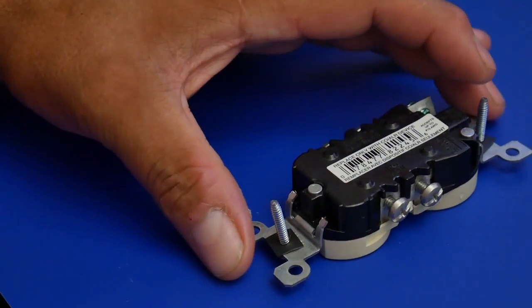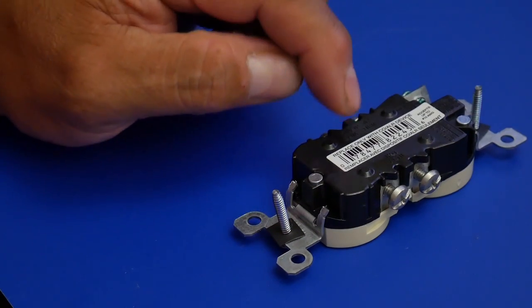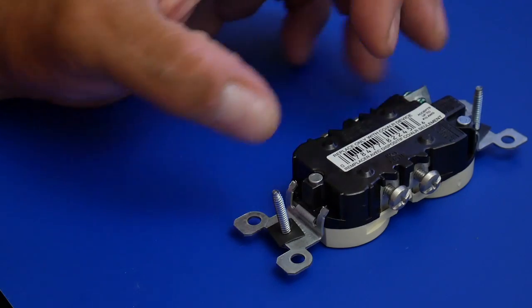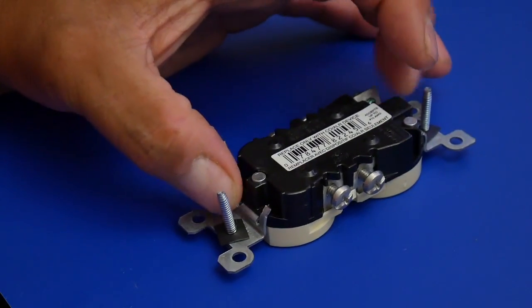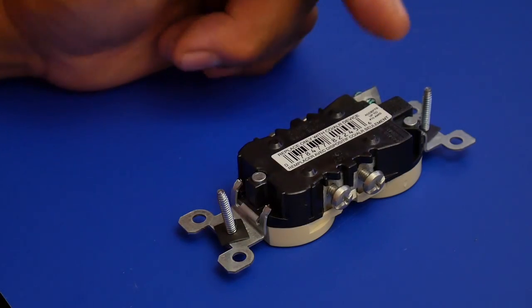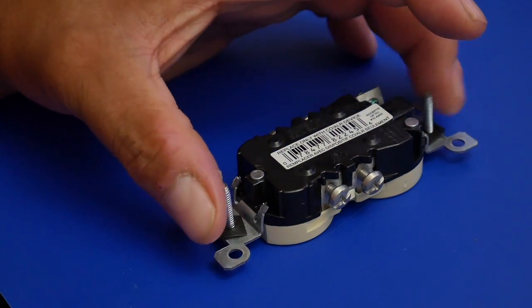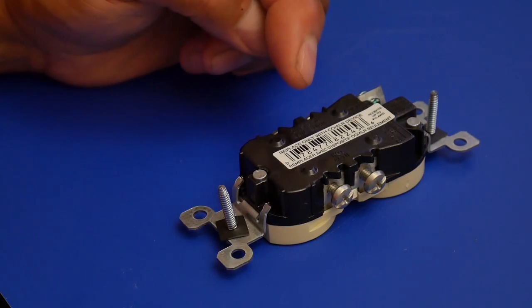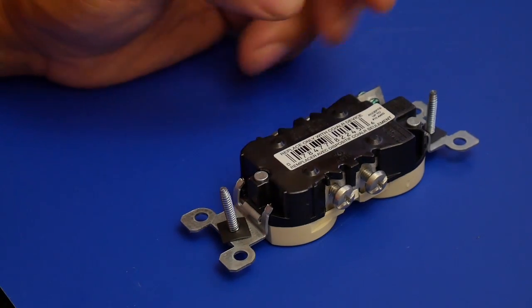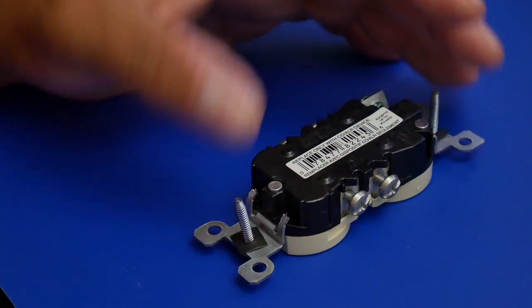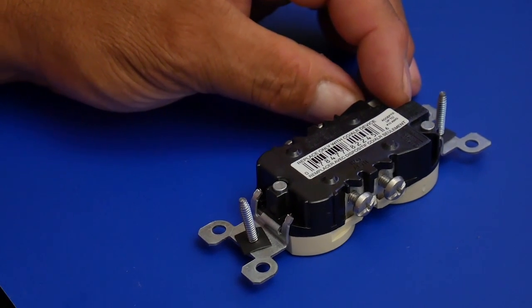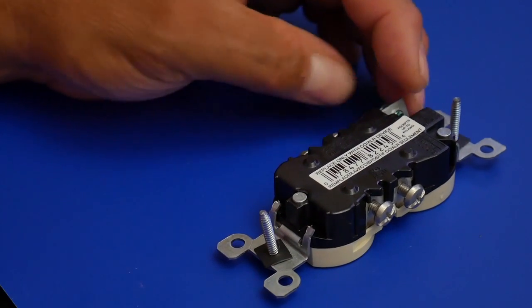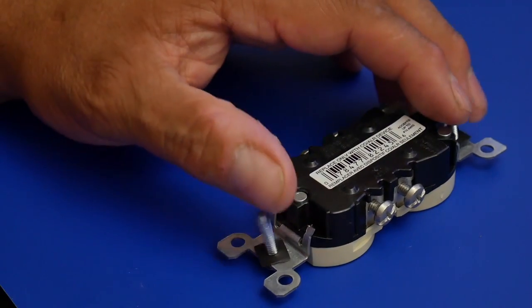One of the other things with the wiring: if you're using a 15 amp circuit you should be using 14 gauge wiring, which is a little bit smaller than 12 gauge. 12 gauge is a little bit thicker and that is for a 20 amp breaker. If you have 14 gauge wiring in the wall, whatever devices you're using, and you're tripping the breaker, you decide 'well I'm going to put a 20 amp breaker where the 15 amp breaker was,' the wiring doesn't support it. It'll overheat and likely cause a fire, so it's actually very dangerous.